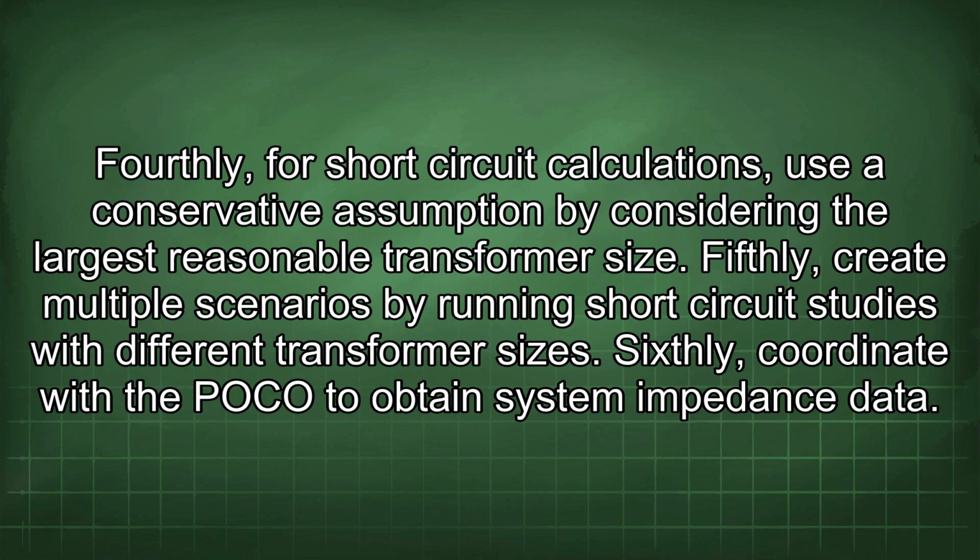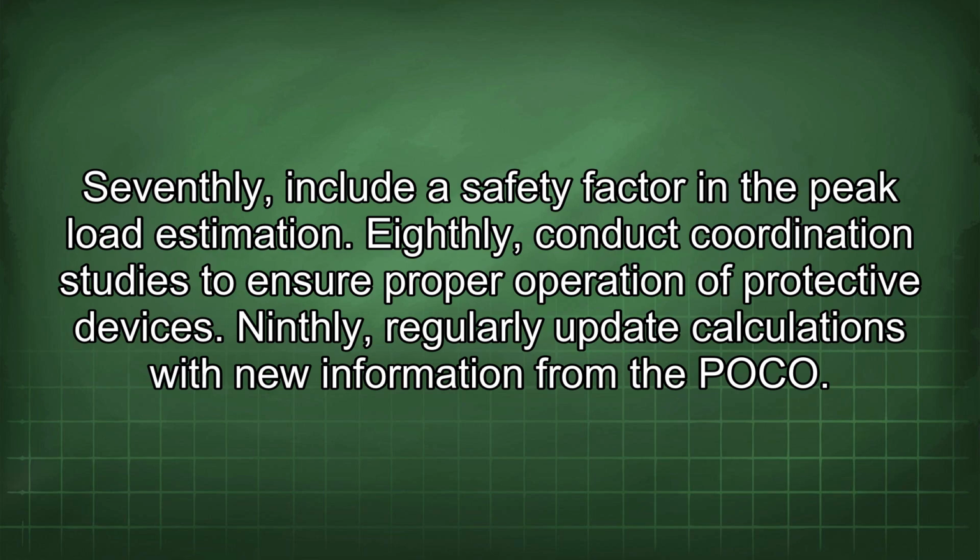Sixthly, coordinate with the POCO to obtain system impedance data. Seventhly, include a safety factor in the peak load estimation. Eighthly, conduct coordination studies to ensure proper operation of protective devices. Ninthly, regularly update calculations with new information from the POCO.